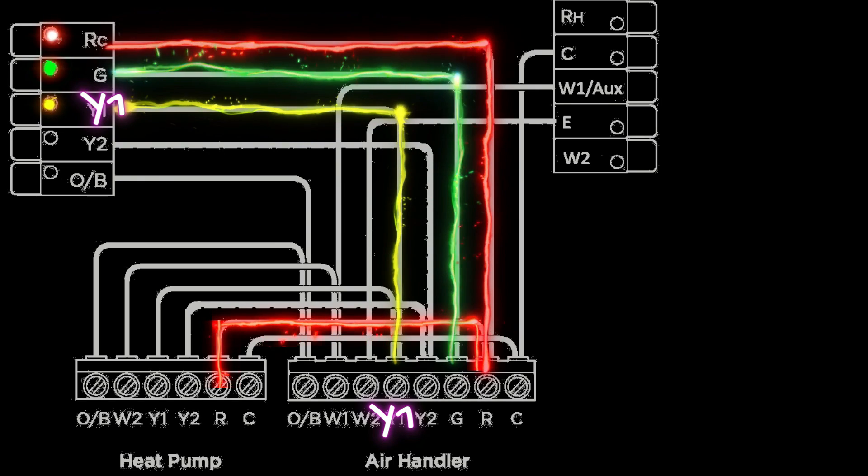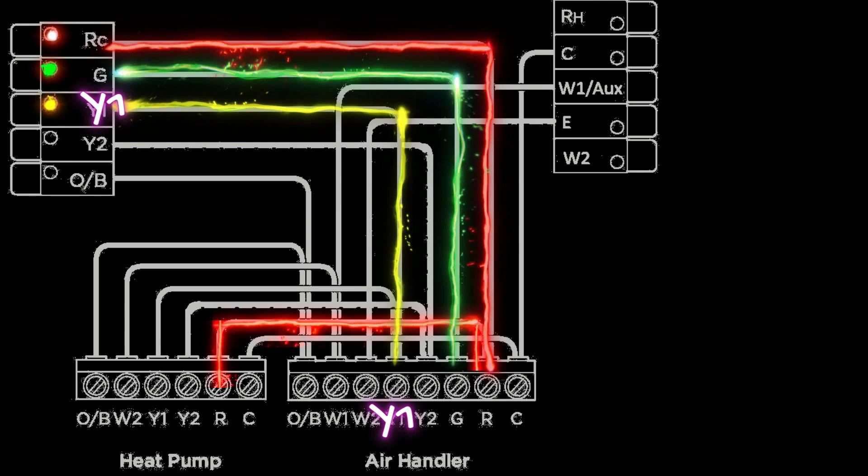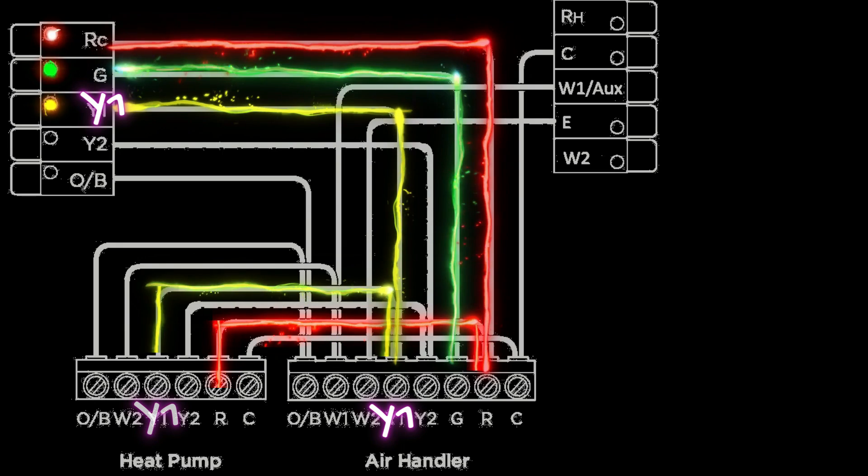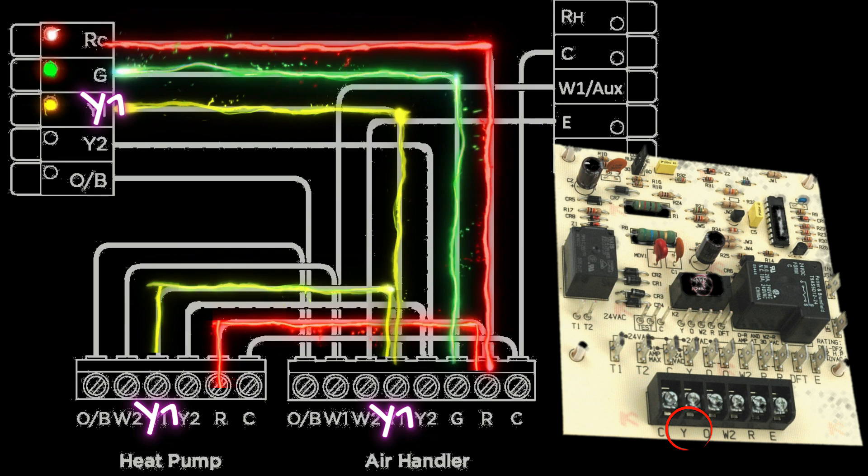Now once our Y1 signal hits that terminal on the control board in the air handler, you're going to have another yellow wire coming off of that same terminal and that is going to go out to the defrost control board on the condensing unit outside.